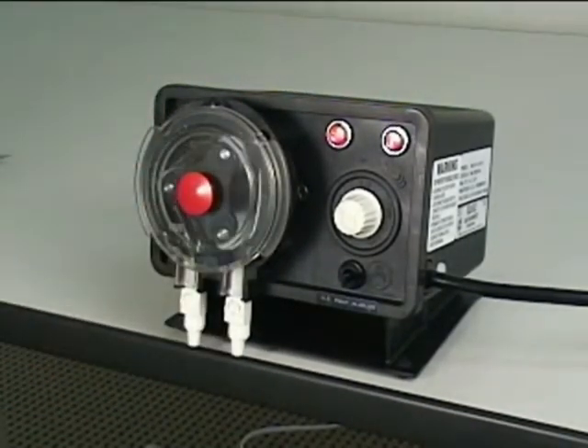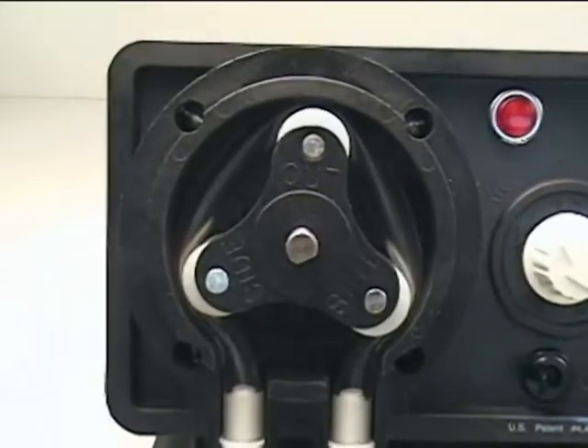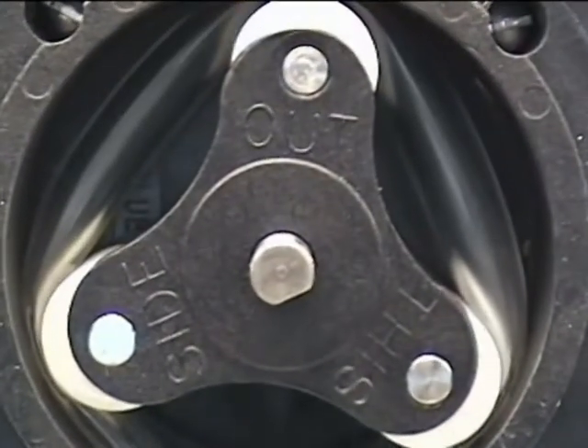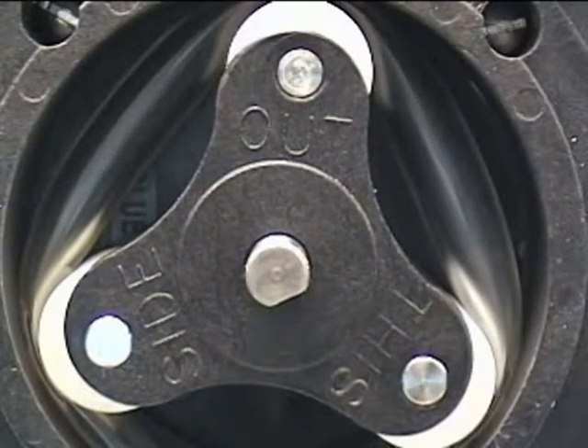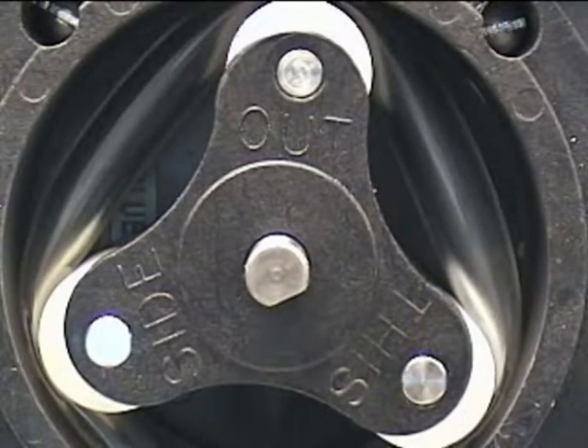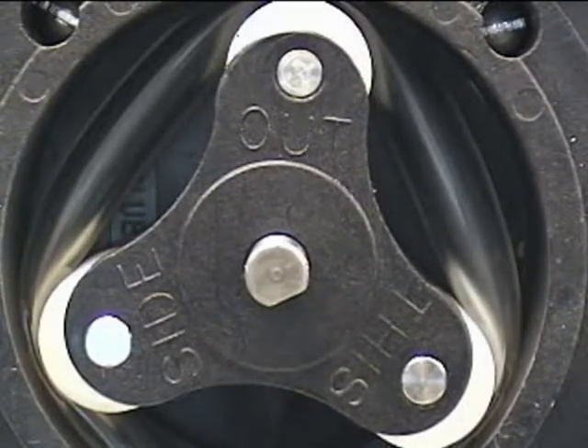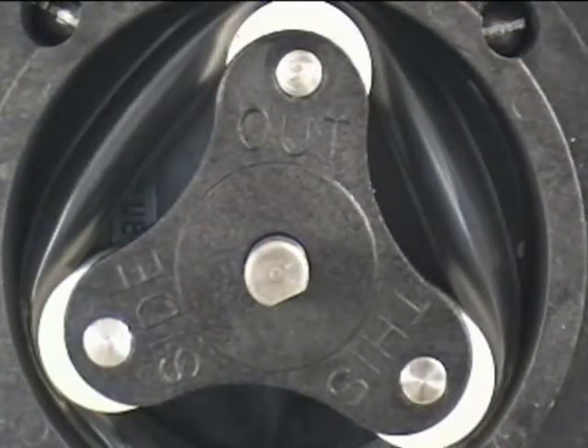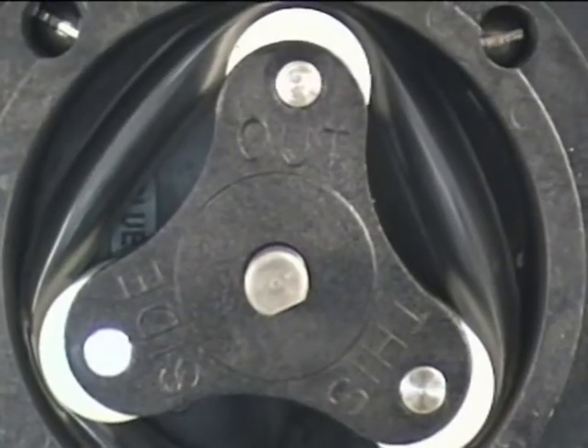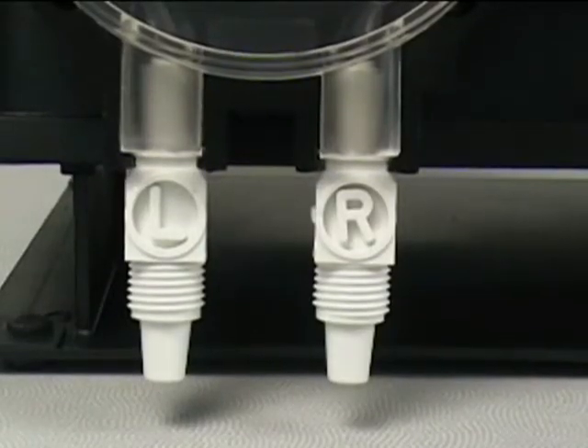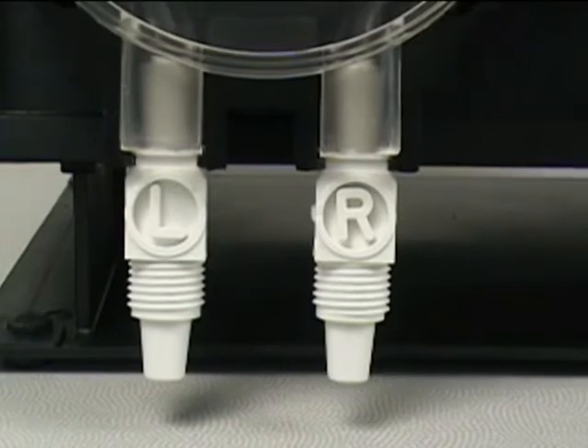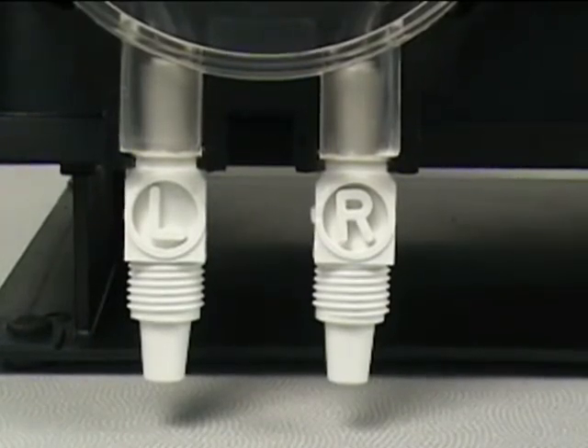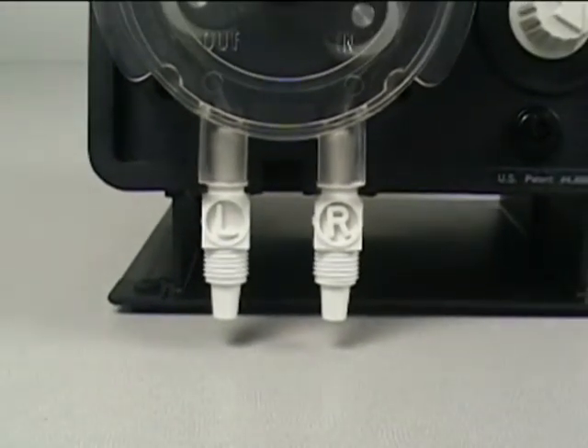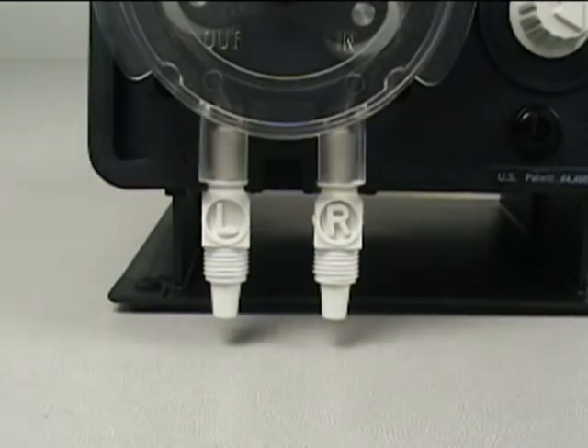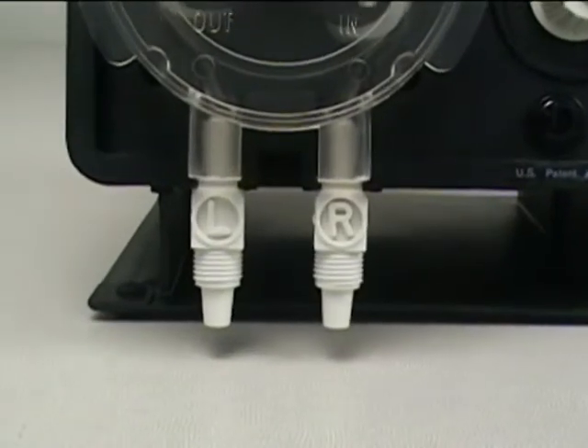Notice the grooves on the pump tube's inlet and outlet fittings. Insert the inlet side of the pump tube, this is the side marked with the letter R, into the right side of the pump head. Be sure the tube fitting grooves slide properly onto the pump head runners. Guide the tube into the head, being careful not to pinch your fingers. Insert the outlet side of the pump tube into the left side of the pump head. Blue White's patented pump tube design will keep the tube properly centered on the rollers. No other adjustments are required.